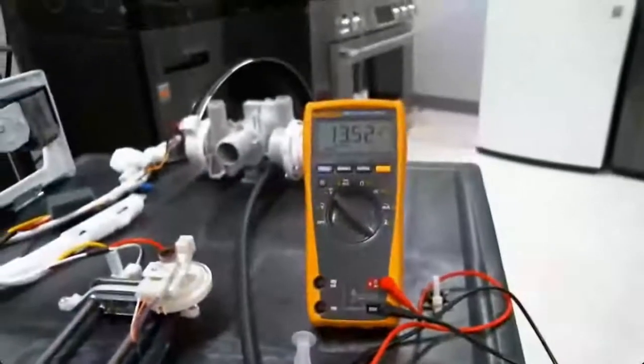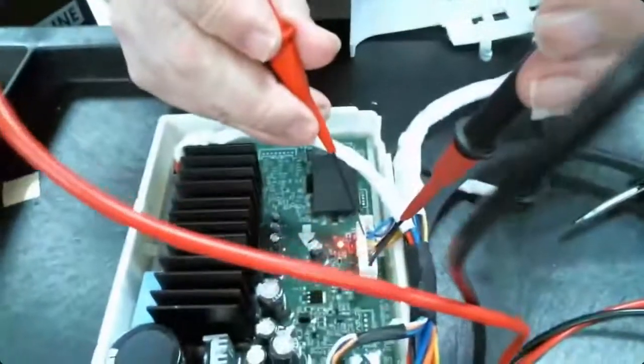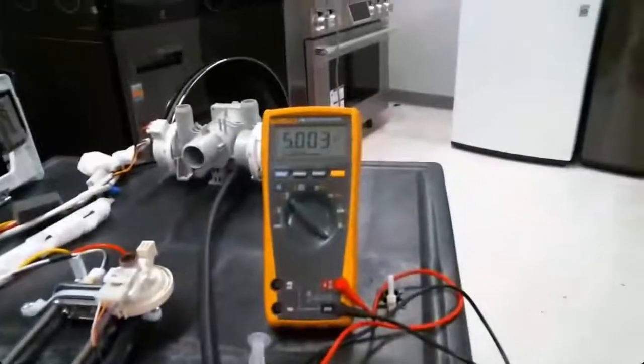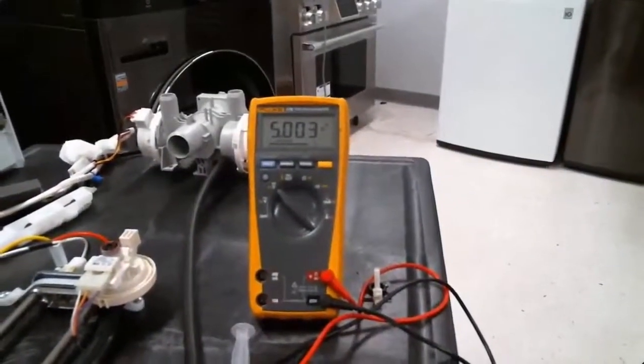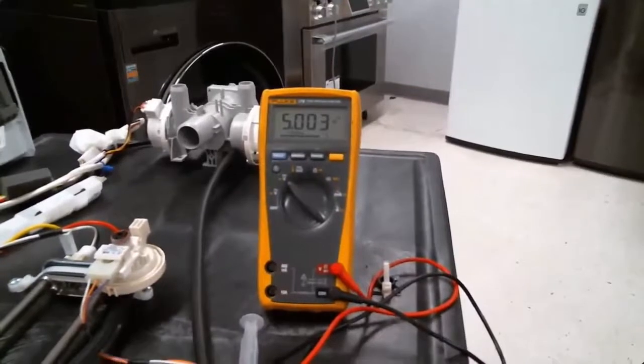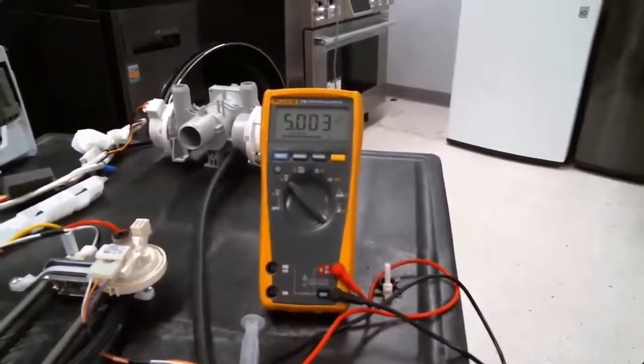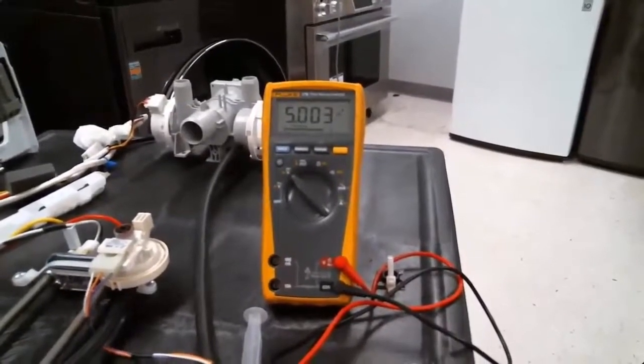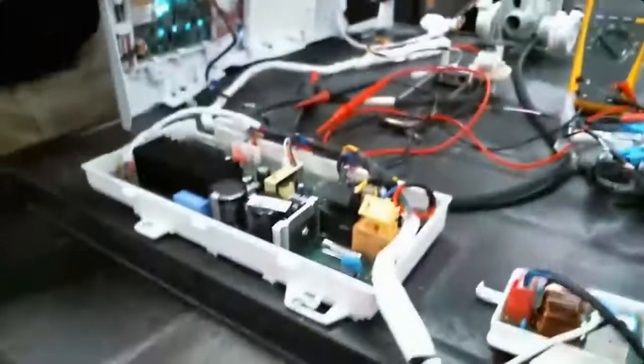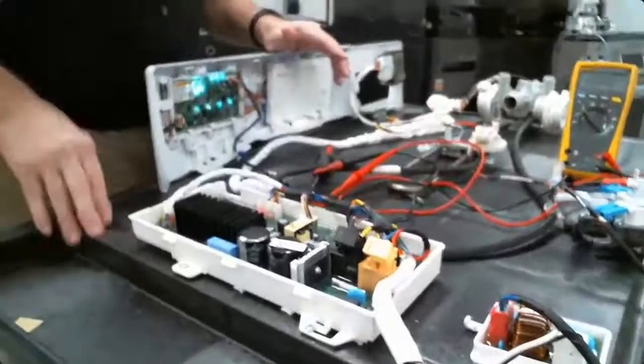Okay, so I got about 13.5 - that's good. The next one is my communication voltage. I go red to yellow, and this should be your 5-volt signal, which I'm using for my thermistor and my pressure sensor. We also use that whenever we have some type of signal. So this is a good way of determining whether my problem is in the main board or the display board. Let me open it up for questions.